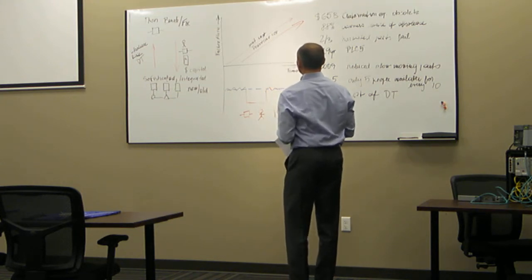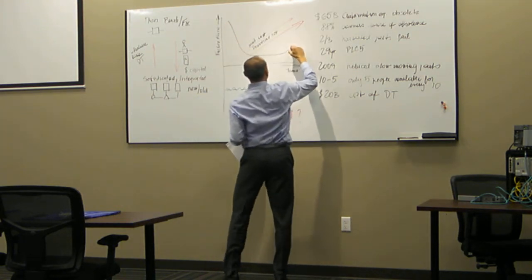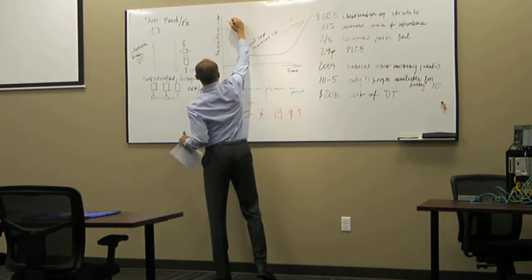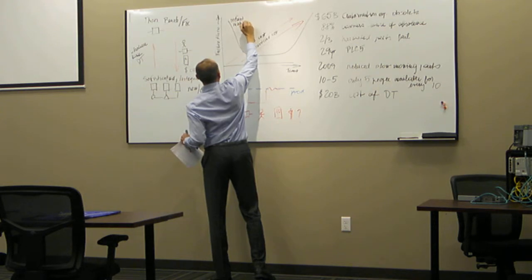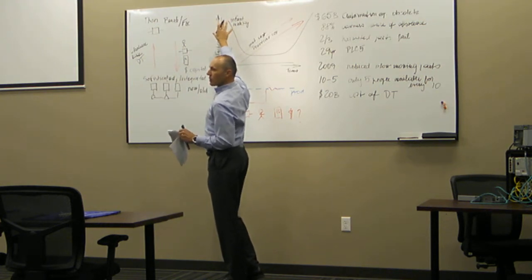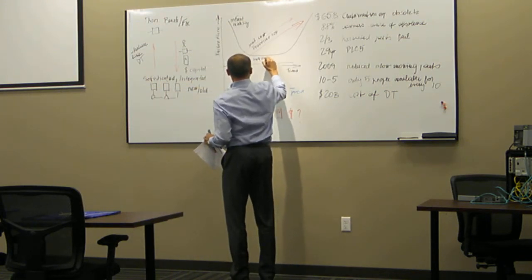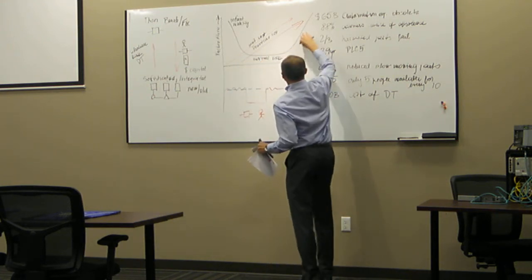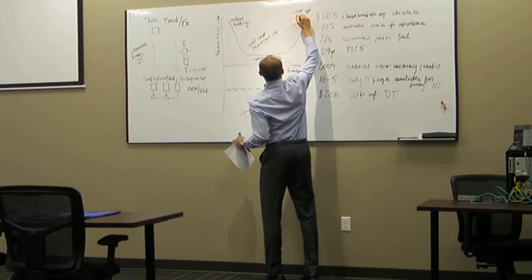So if you look at it from the perspective of electronic equipment, there is the life cycle curve of electronic equipment. I don't know if you ever seen it. It's the bathtub curve. So this is where we can expect some infant mortality. The electronic equipment usually fails very soon if it's going to fail. But if the establishment is running, there is a normal life of that equipment. But as it's getting older, the possibility of failure increases. So this would be the end of life.